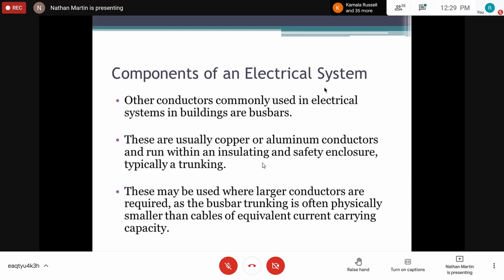So rather than have a whole heap of different meter sockets mounted on a wall, they create what is known as a bus bar chamber. With the bus bar chamber, all they do is mount the jacks or the sockets for the meters, right? So JPS would come and power the bus bar. From your service drop wire, that's the wire coming from the pole to your potted connection, and then from your potted connection to your bus bar chamber, and the bus bar chamber will distribute to the different meters, and then from the meters you'll have the connection to the different residents within the building, right? In fact, when JPS come, all they need to do is go to the metering room and read all the meters in one place, instead of having the meters scattered all over the place. So this is really one application of a bus bar chamber.